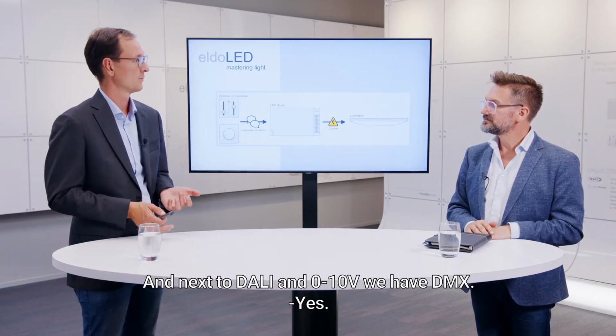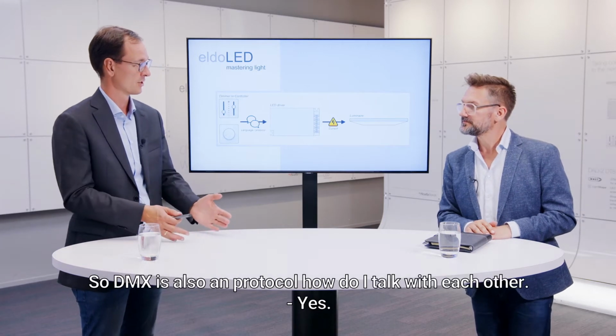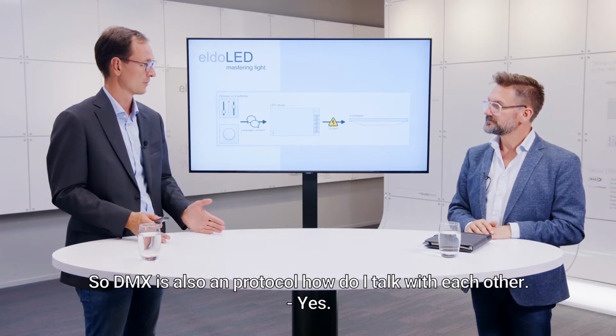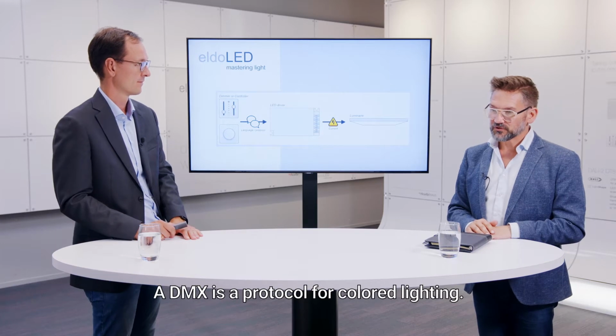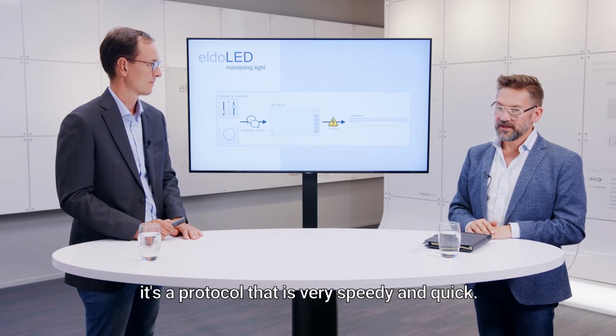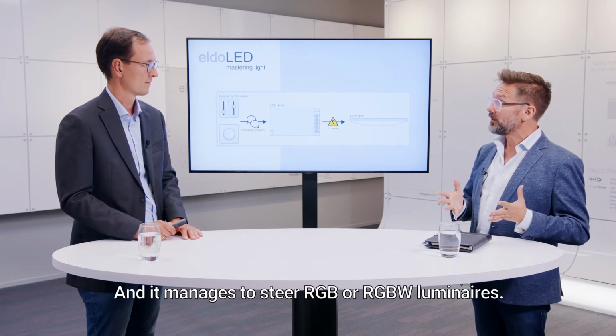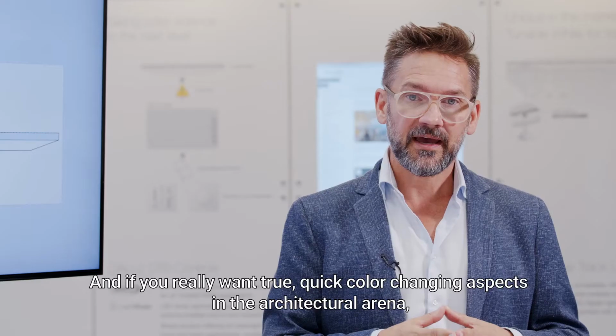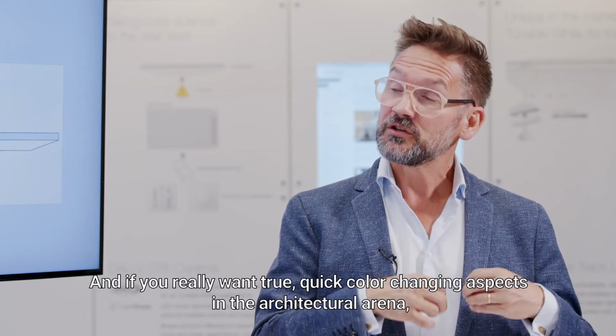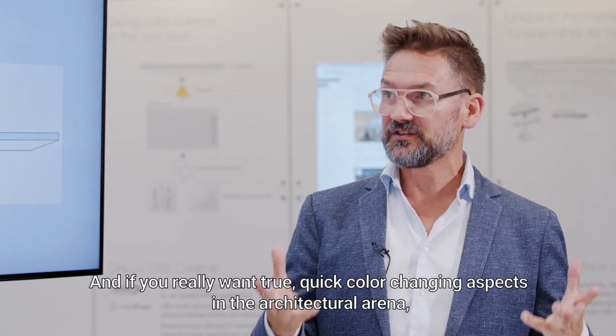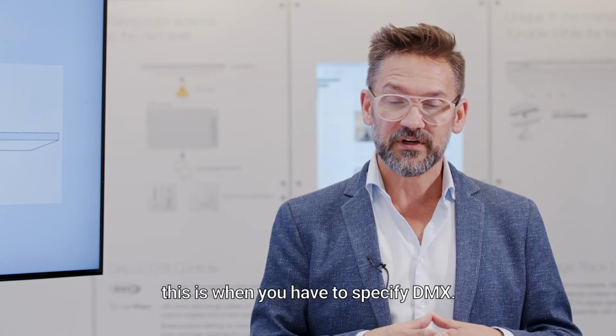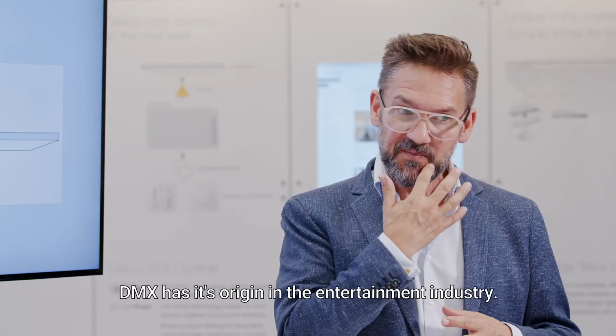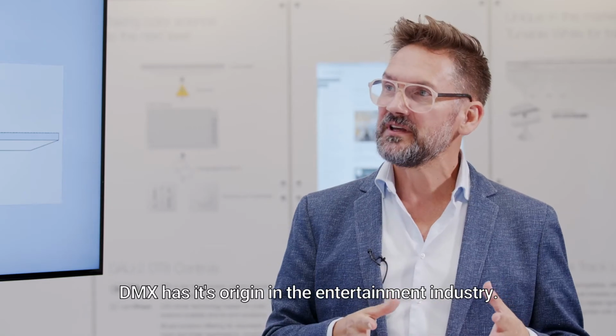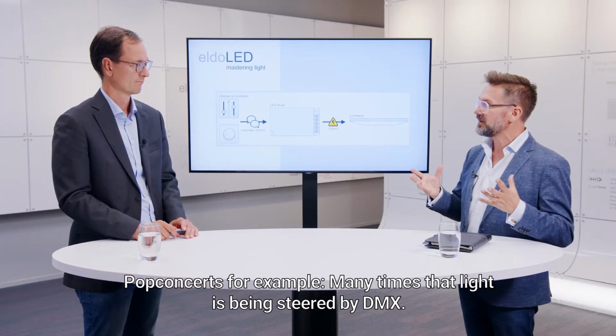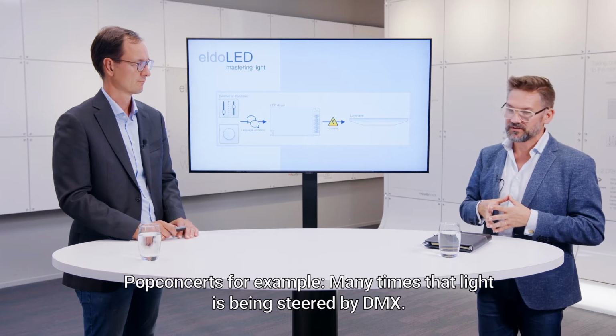And next to DALI and 0 to 10, we have DMX. Yes. So DMX is also a protocol. How do I talk with each other? Yes. DMX is a protocol for colored lighting. It's a protocol that is very speedy, very quick, and it's managed to steer RGB or RGBW luminaires. And if you really want true, quick, color-changing aspects in the architectural arena, this is when you have to specify DMX. DMX has its origin in the entertainment industry. Pop concerts, for example, all that light many times is being steered with DMX.